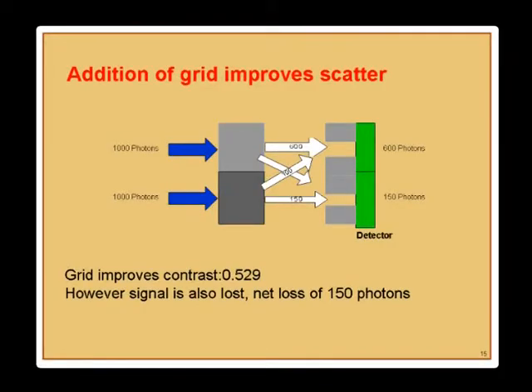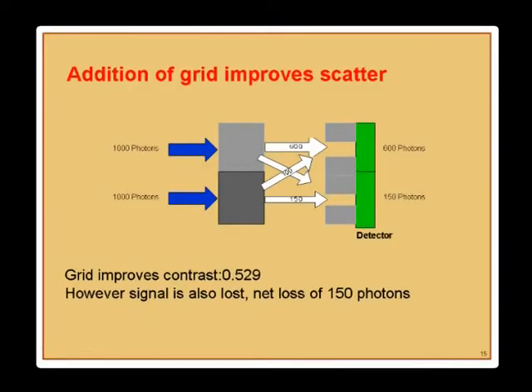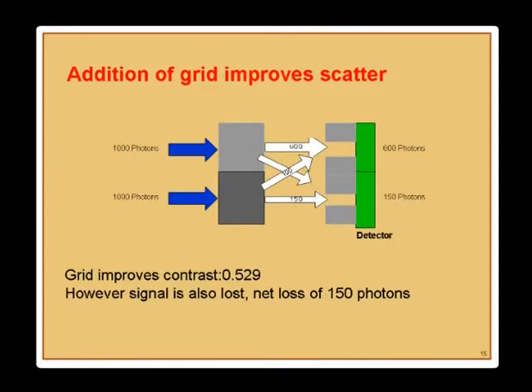If you don't do anything about scatter, you lose contrast. To address this, a grid is placed over the detector which impedes photons coming in at an angle — depending on the shape and size of the grid — so only photons coming straight through are caught at the detector. This improves contrast, but we lose photons. Normally this wouldn't be an issue, but noise will enter the picture and affect contrast.